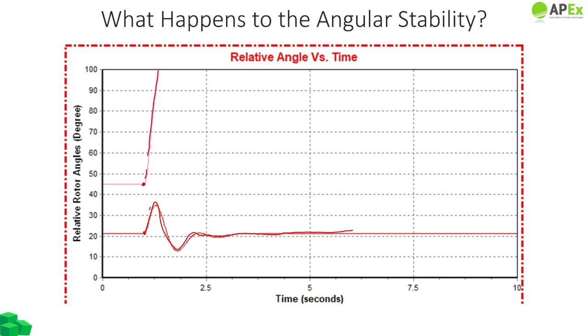So what does this signify? Let's try to draw a conclusion here. For very long transmission lines, even though the system appeared to be stable in steady state with regard to voltage stability, it is not stable in the transient or dynamic analysis, particularly with regard to rotor angle stability, or angular stability. Limiting the flow on that particular line would help us make the system stable. So the limiting factor for very long transmission lines is actually the rotor angle stability.